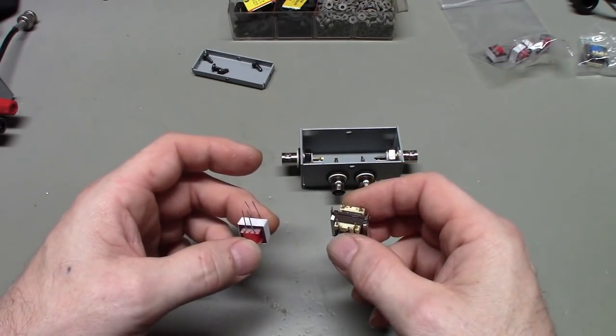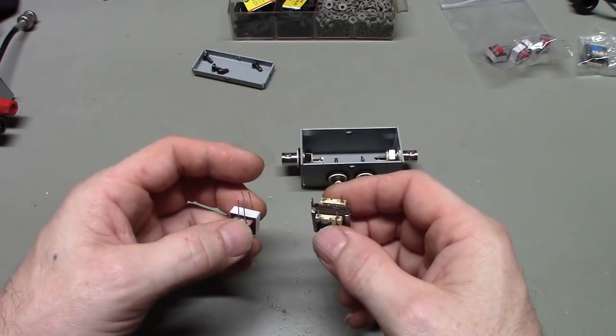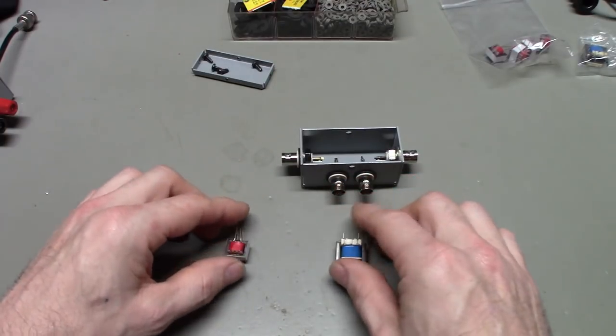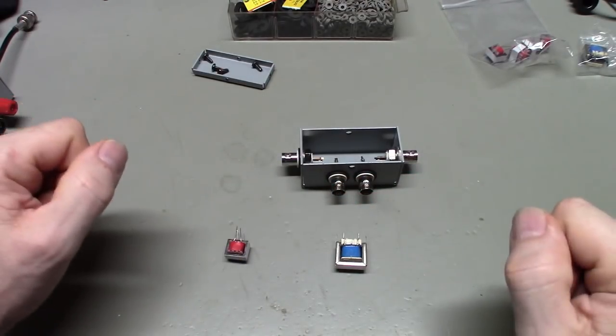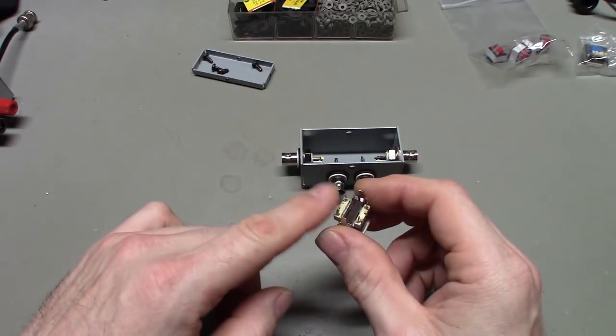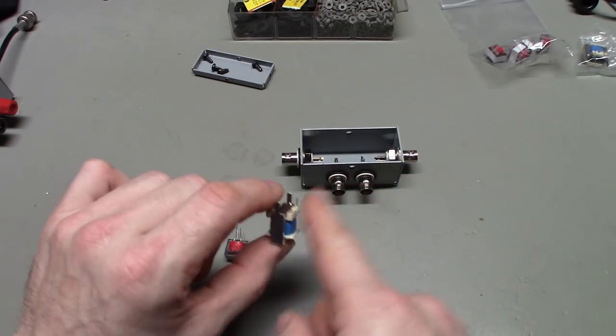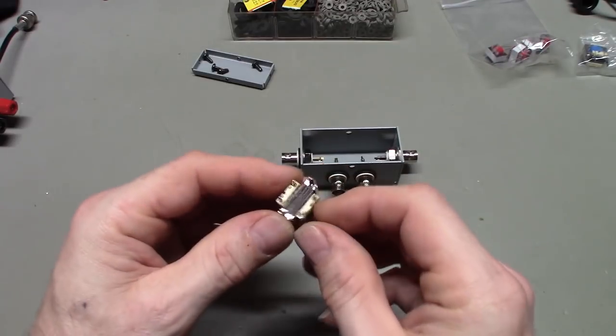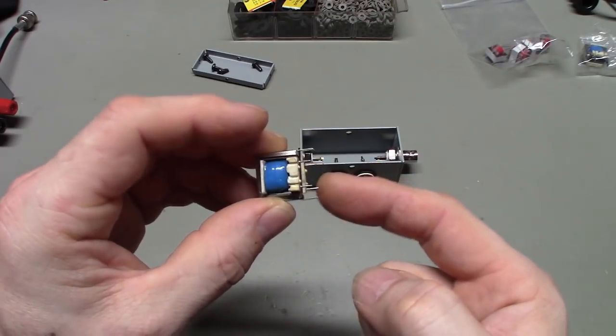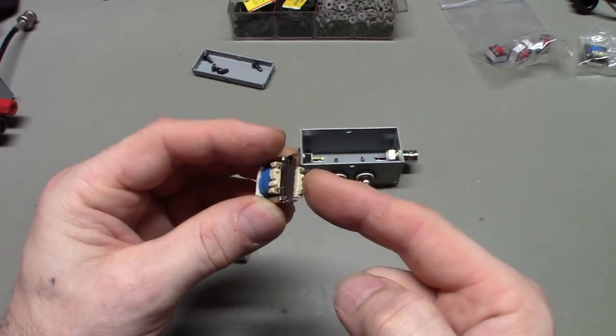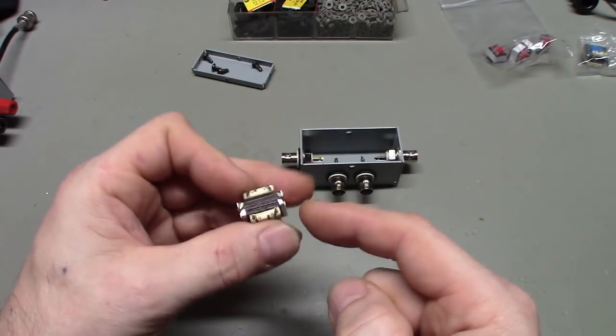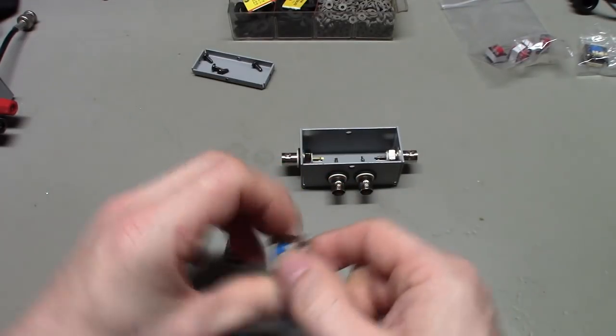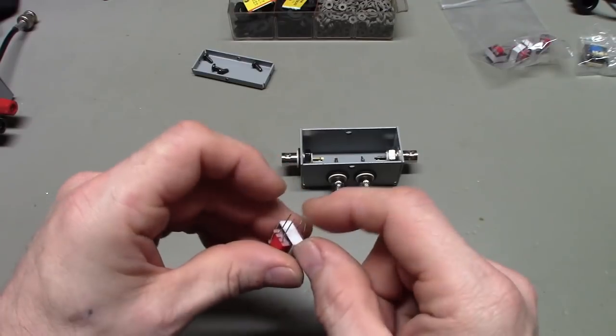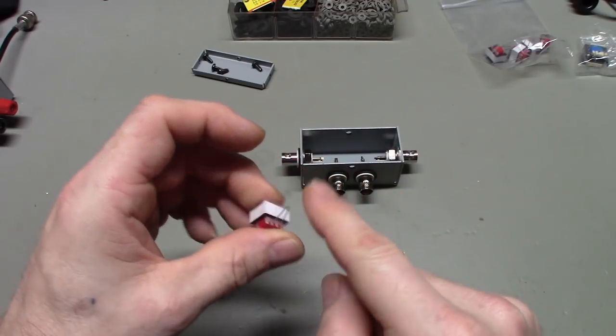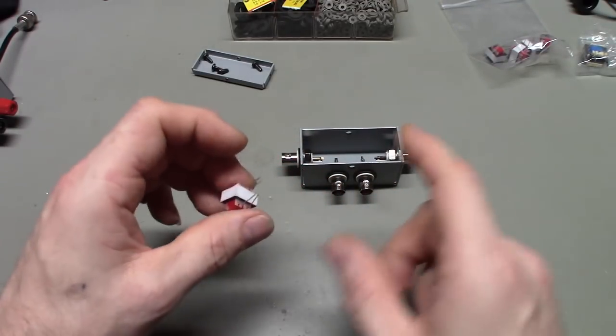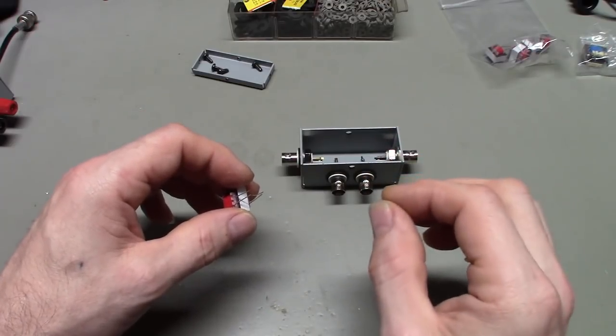These aren't really transformers in the sense that they're not transforming anything - there's not one impedance on the input and a different one on the output. The impedance on both sets of terminals is exactly the same: 10,000 ohms on one side and 10,000 ohms on the other. Same thing with the 600 ohm - one side is 600, the other side is 600. All it's doing is isolating it.